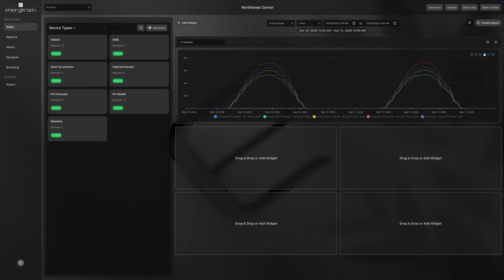We provide 4 different PV power models. We provide IEC 61724-based DC and AC models. These follow international standards for PV performance monitoring, but do not fully account for real-world losses such as temperature, wind, or panel degradation, which means they are not always accurate.